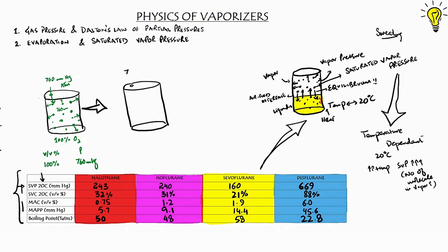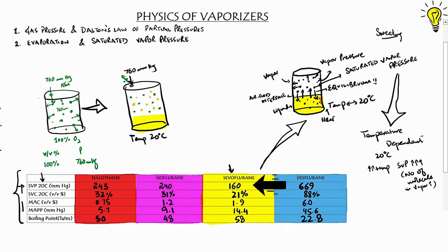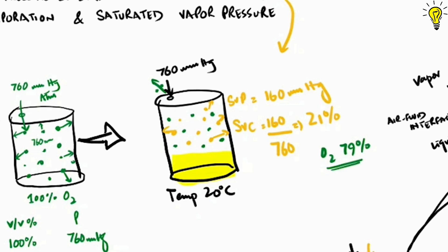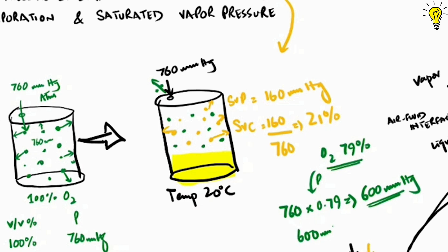Let's place sevoflurane now in the first chamber with oxygen at 20°C. It would generate a saturated vapor pressure of 160 mmHg. In terms of Dalton's law, the partial pressure of sevoflurane is 160 mmHg, so volume-by-volume concentration would be 160 ÷ 760 = 21%. If sevoflurane vapor is exerting 21% pressure, the remaining pressure is exerted by 100% oxygen at around 79%. So partial pressure of oxygen would be 760 × 0.79 = 600 mmHg. So 600 + 160 of sevoflurane gives a total pressure of 760 mmHg — the same as ambient pressure.